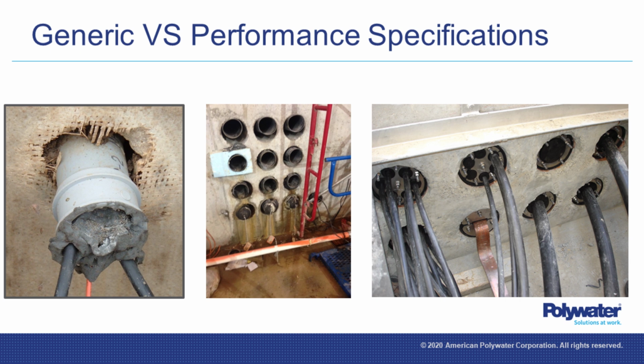And by far, as I mentioned previously, let's say that your utility does a lot of directional boring where you've got some wiggles, but it's hard to tell where they are. Or you have an existing conduit system that, even though you used a good pulling practice where you mandreled or brushed out the conduits, you still got mud and some dirt in there. By measuring and requiring people to record the ending tension, that is, when the head end of the cable exits the end of the conduit system, look down on the tensionometer, dynamometer, write that down and back calculate it. That is going to be the best tool for you to help pull longer.